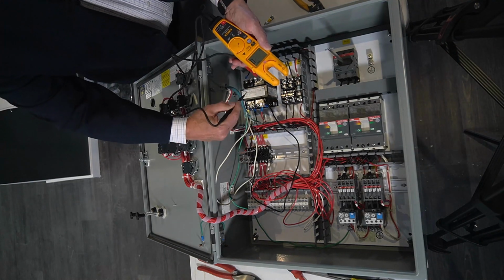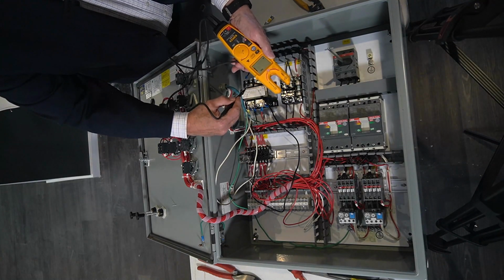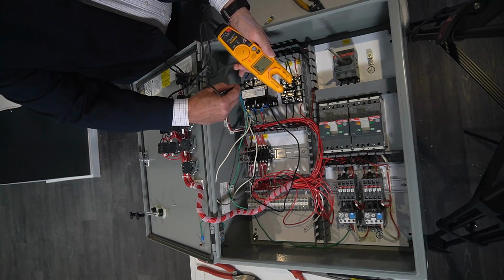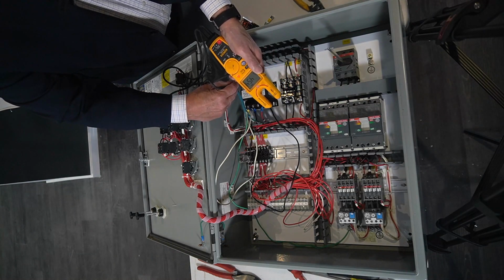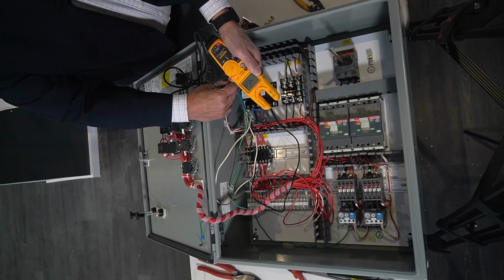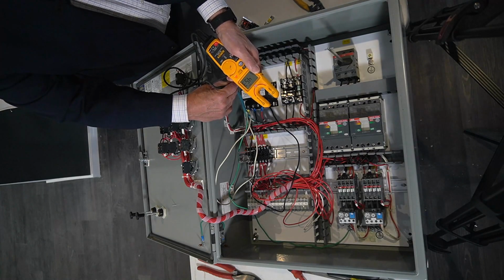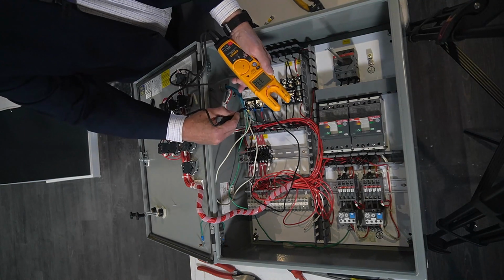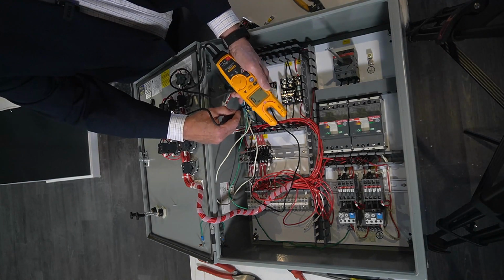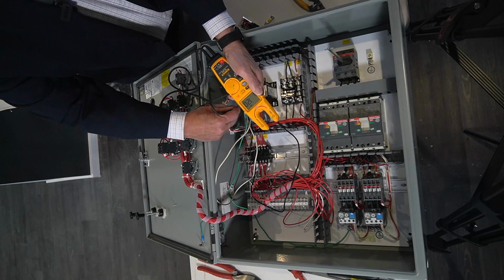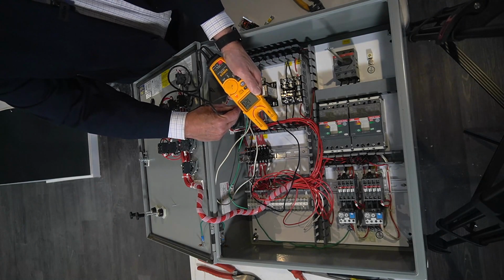Now the primary would be normally where I receive my power, but since this is a linear device, you can see there's 454 volts on the primary of the transformer. So this is where the 480 would come in, and the 120 would provide me with my control voltage. So that'd be the 120 volt controls.